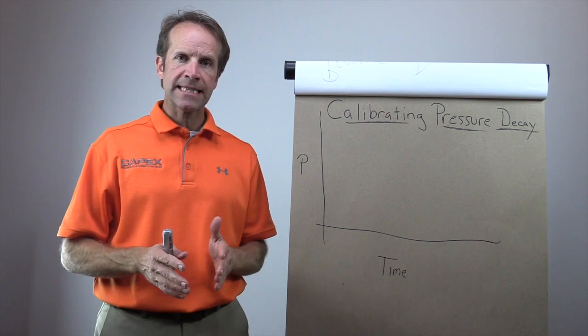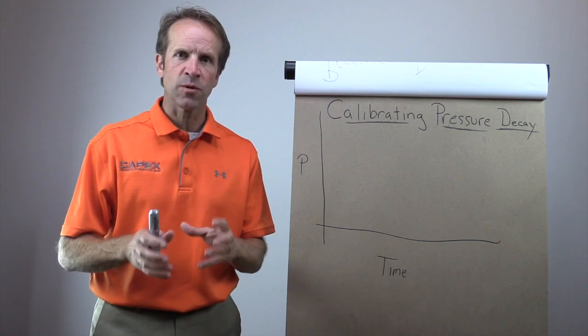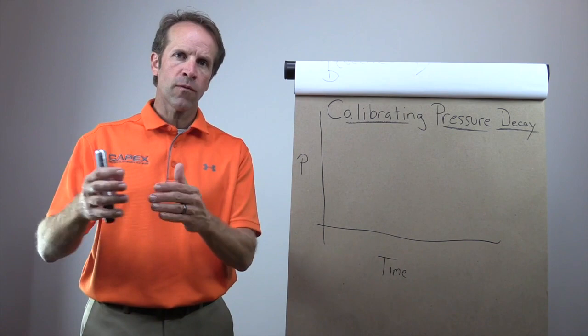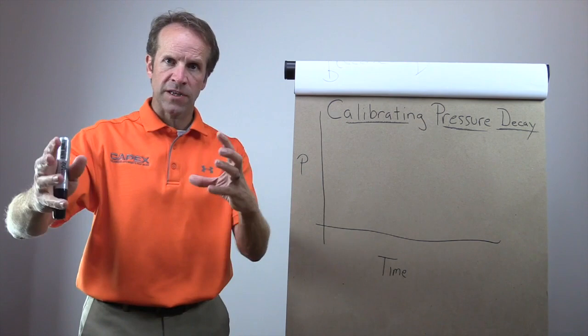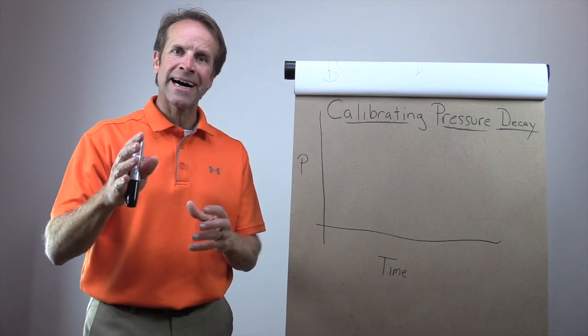Let's talk about pressure decay leak testing. Pressure decay leak testing is a measure of pressure loss over time. So we pressurize a part and we measure pressure loss out of that part over a specific amount of time. Theoretically, I've got my instrumentation connected to a part that is fixtured. We seal the part, we pressurize the part, and we are going to then isolate the part.